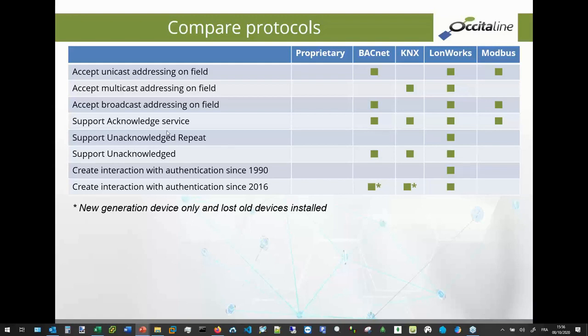A multicast is one push button to 1,000 lamps. In this case, BACnet does not support that. KNX supports only that, and LON supports that. Modbus does not support multicast. And at the end, broadcast is supported by KNX, sorry, LonWorks and Modbus. But on the field, for the connection, multicast is always used.